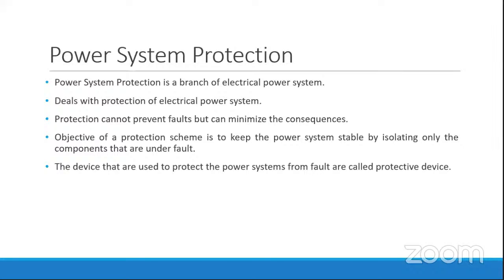The objective of a protection scheme is to keep the power system stable by isolating only the components that are under fault. Let's say a short circuit occurs in one motor. Only that motor feeder gets isolated from the system, and the entire network should not be interrupted. Power to the healthy system should be continued.